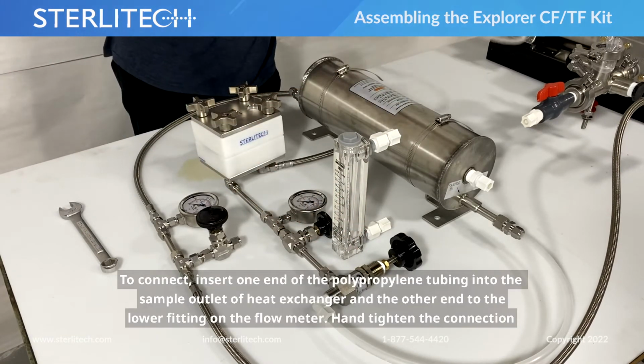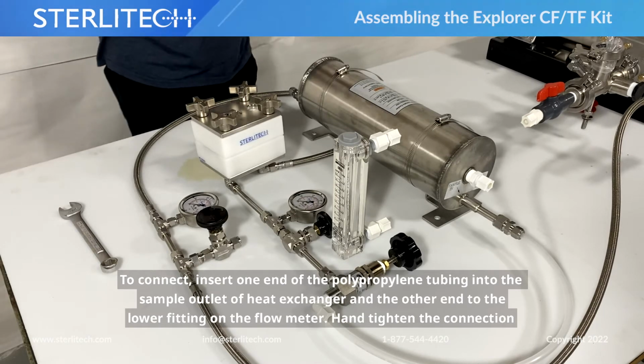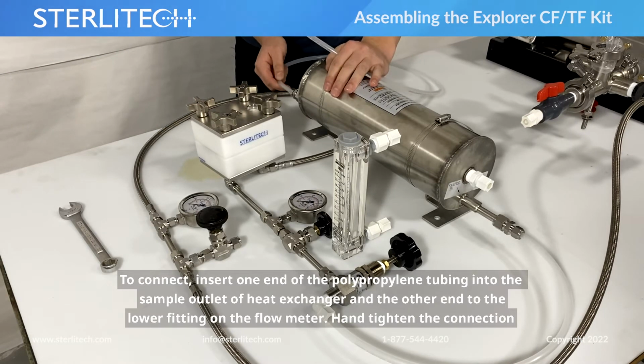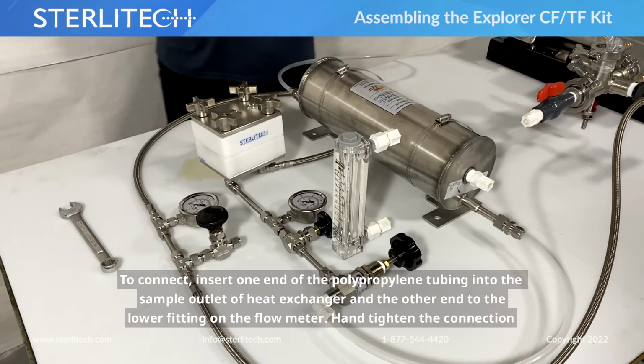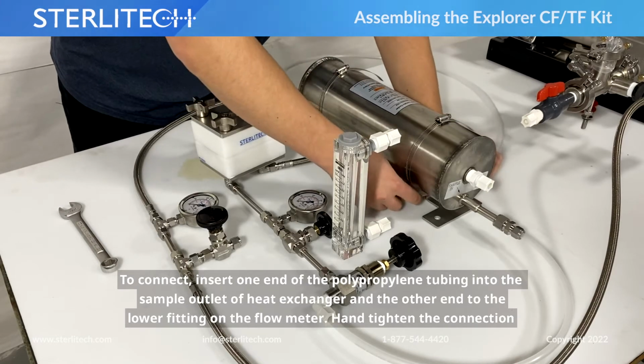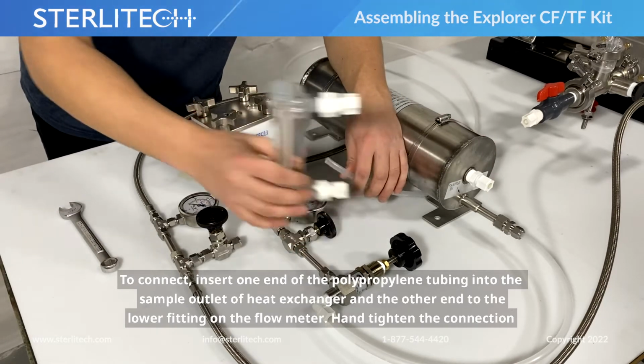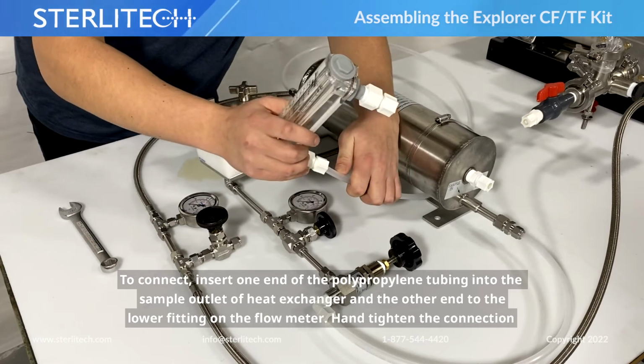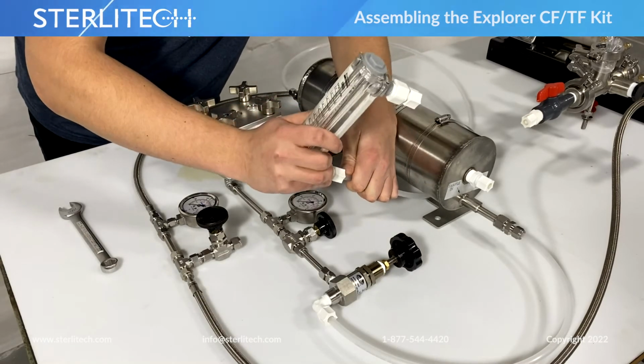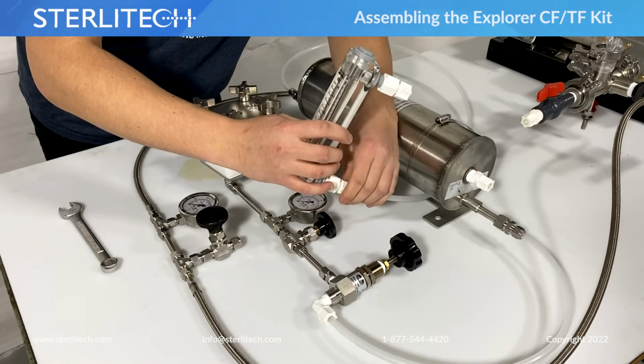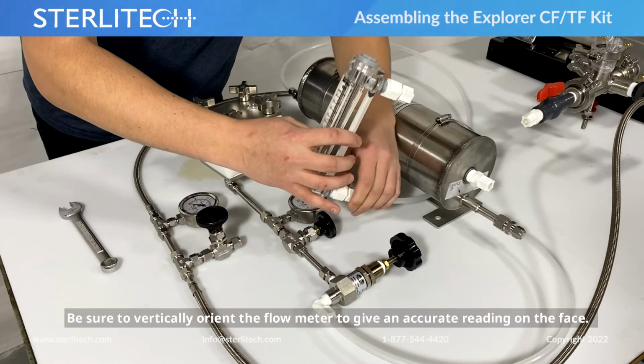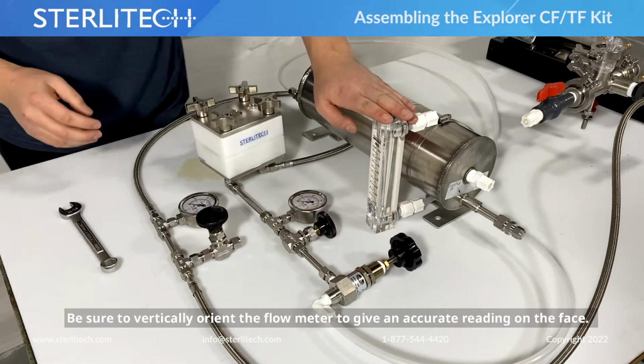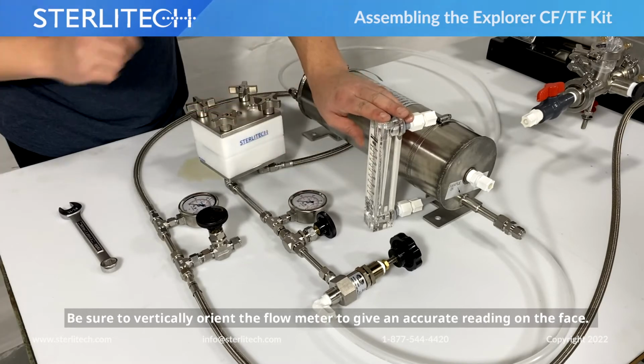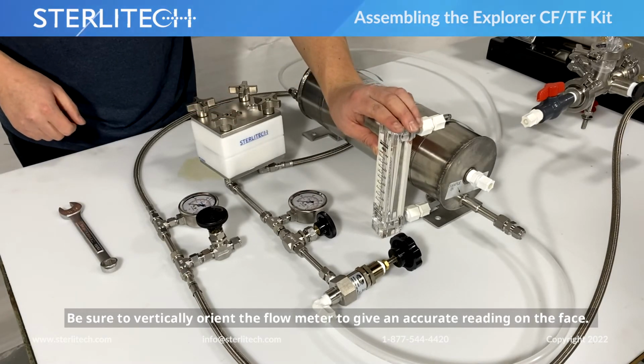To connect, we're going to use some more polypropylene tubing. We're going to put one end into the sample outlet of our heat exchanger. The other end, we're going to route into here and connect to the lower fitting on your flow meter, that is the inlet. There we go, you just tighten that down as well. One thing to note is you're going to want your flow meter oriented vertically, or else it's not going to give you an accurate reading on the face. Okay.